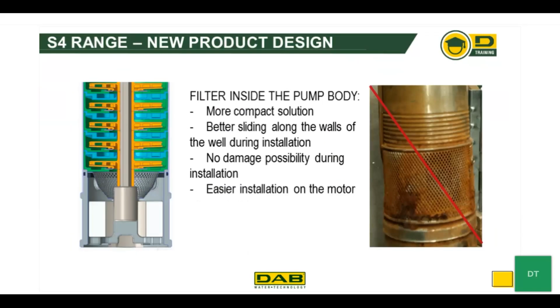Filter inside the pump body. It's now a more compact solution. It makes it easier to move along the walls of the well during installation so that there are no snags. There's no damage possibility during installation because it's already integrated into the pump and you don't have to add it on after the pump is connected to the motor. And it makes for an easier installation on the motor because, again, it's not an additional part that you have to add. It's integral to the pump.